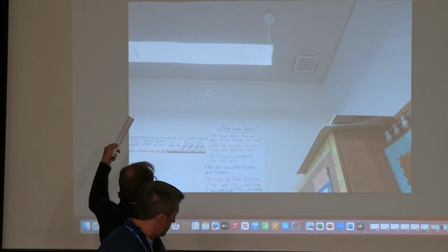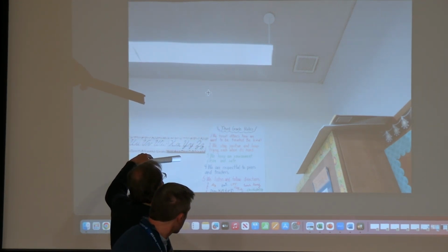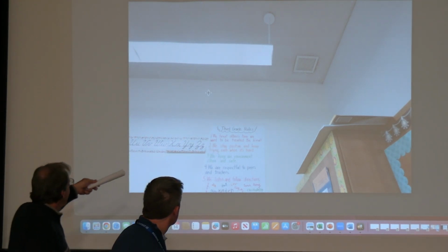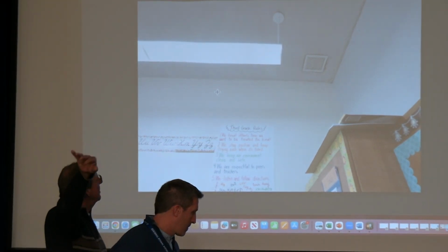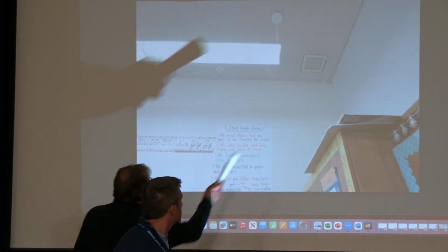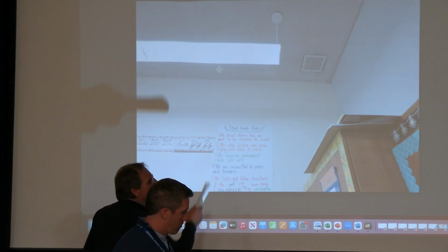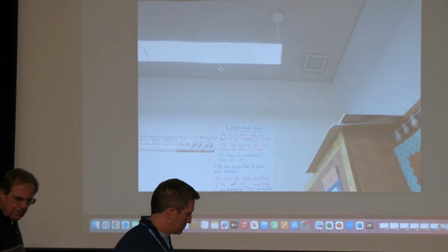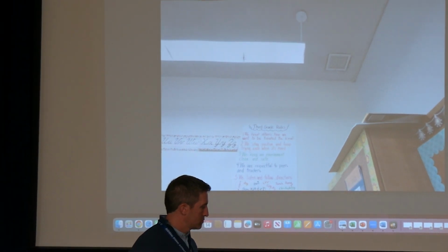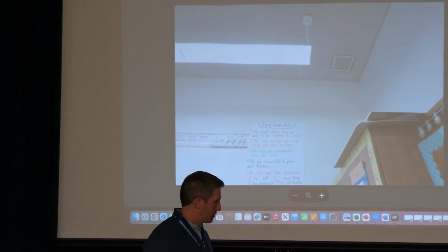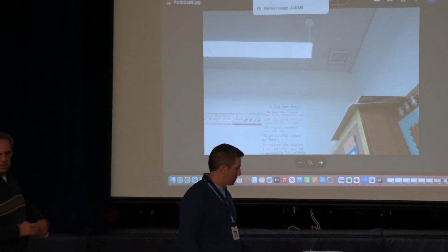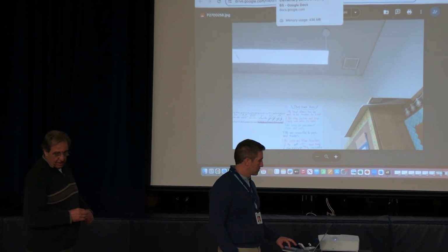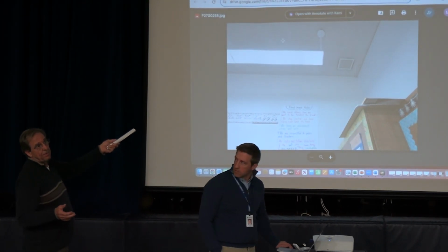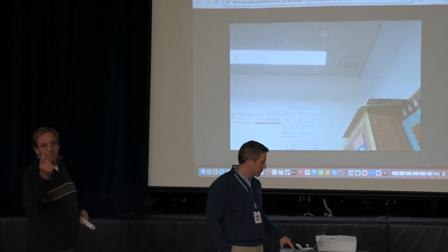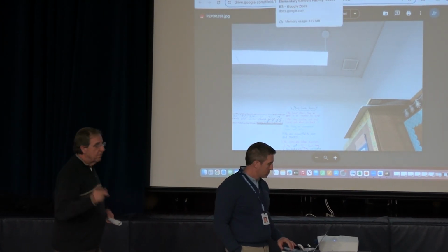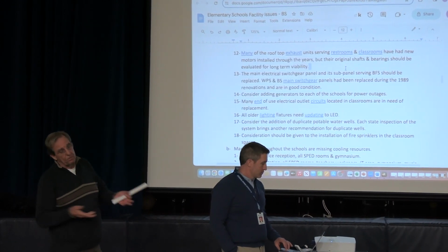Each of the classrooms—this is, where am I? I'm not sure, I lose track of some of them. This is at the top of the stairs, I think, on the right. In the ceiling there's a grate, and if you calculate that, that's 100 CFM, so it'll take 100 cubic feet a minute of air through the grate. That room, if it were 20 by 30 and 10 foot tall, would be 6,000 cubic feet of air, so that thing will take 6,000 cubic feet an hour. So the air exchange in that room is one time an hour, and that's if the windows open, because the only place for the fresh air to come is through the window.